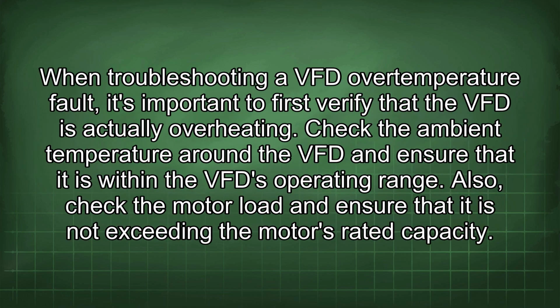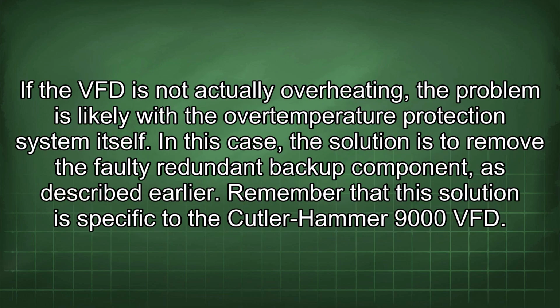When troubleshooting a VFD overtemperature fault, it's important to first verify that the VFD is actually overheating. Check the ambient temperature around the VFD and ensure that it is within the VFD operating range. Also, check the motor load and ensure that it is not exceeding the motor's rated capacity. If the VFD is not actually overheating, the problem is likely with the overtemperature protection system itself. In this case, the solution is to remove the faulty redundant backup component as described earlier.